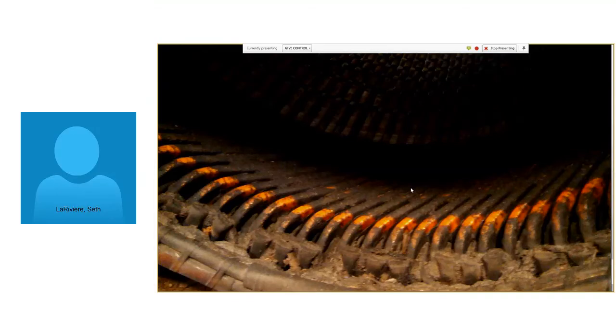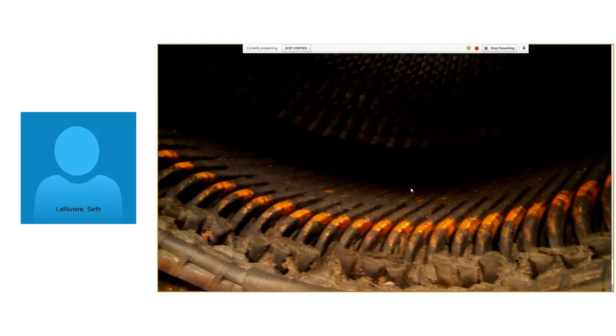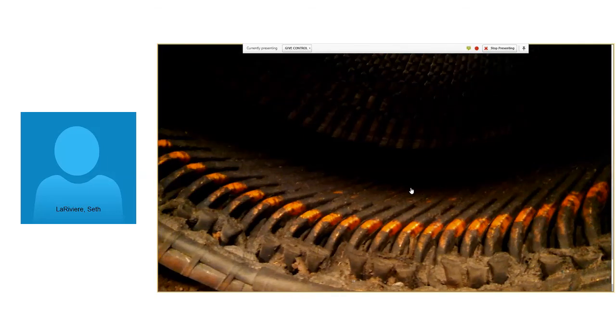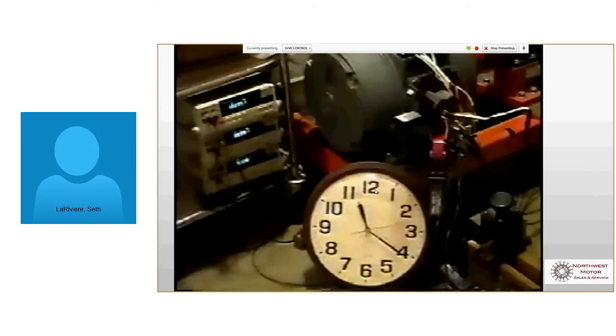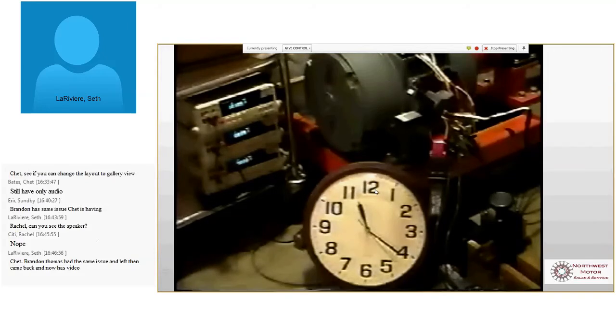motor fails. And why we're showing this is, I'm going to talk about testing after Ed's done, that's why it's good to predict when you have a turn-to-turn problem in a motor, because a turn-to-turn short is the beginning of the end, as you'd say in the other video that didn't work. Right? And so you can see it's been about 30 seconds. Hopefully we'll see this. I think real soon you'll see smoke start pouring out of the motor. And this is a turn short at operating voltage. You can see the smoke now.